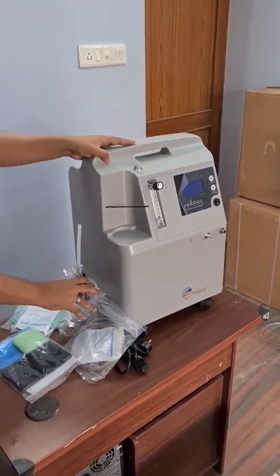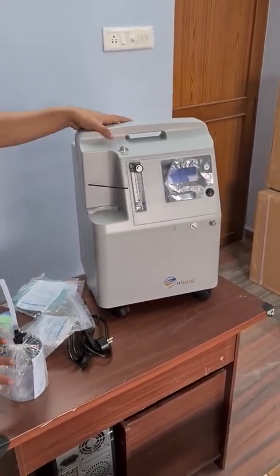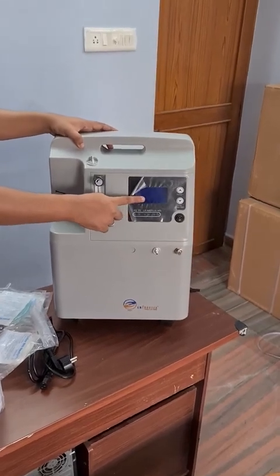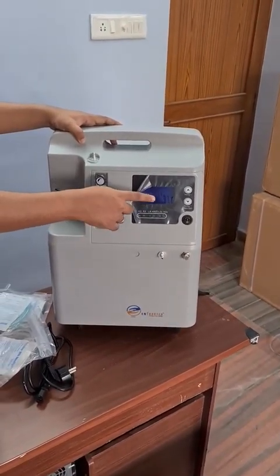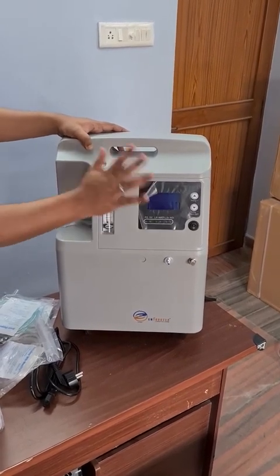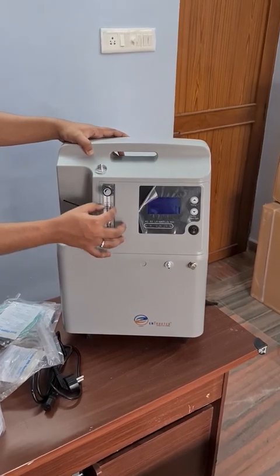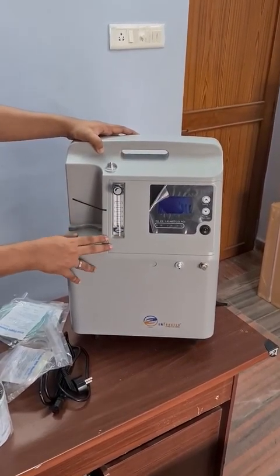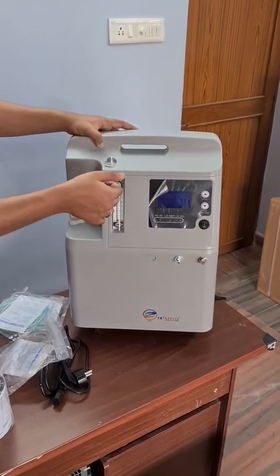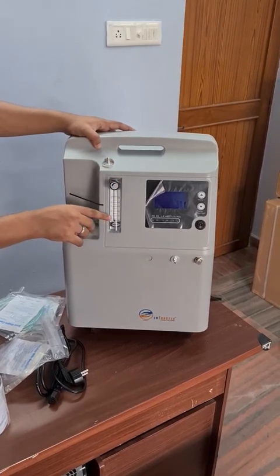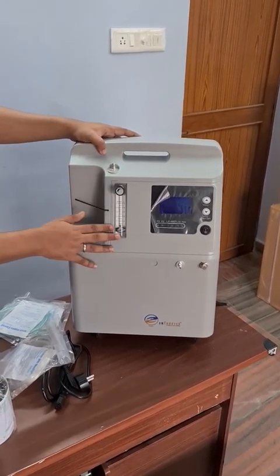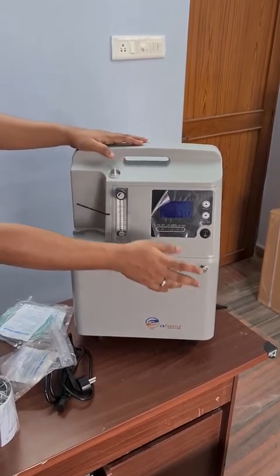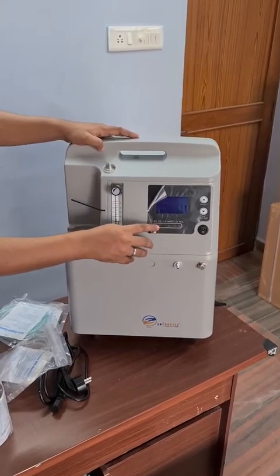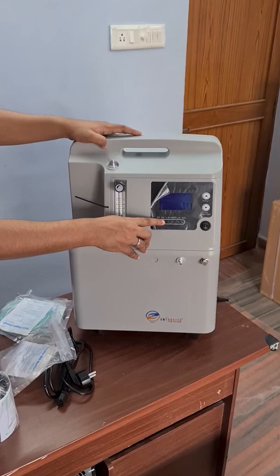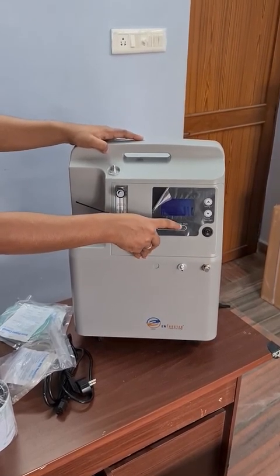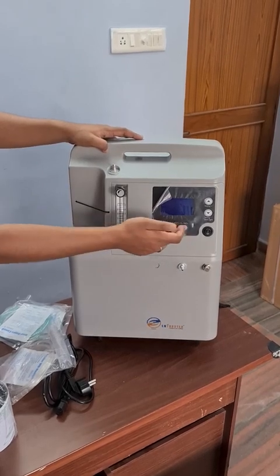Okay. First I'll explain the buttons and ports available on the concentrator. There is a digital display which shows the accumulation time, switch times, and the output pressure coming from the device. There is a knob to adjust the flow rate. Say, for example, your doctor has prescribed 2 liters per minute of oxygen. You need to rotate the knob anti-clockwise to set it at 2. Once you keep it at 2, you can remove your hand and the setting will be stored in the device. This is the on and off button, and these are the indicator alarms: power on, power failure, low pressure, high pressure, low oxygen and high oxygen. Once you switch on the device, I'll explain in detail.